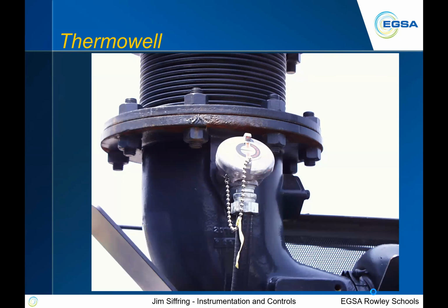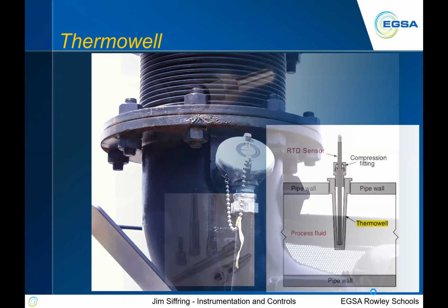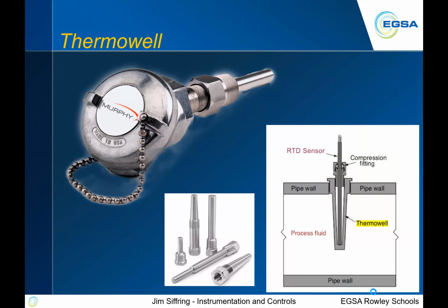A thermowell. So what is a thermowell? A thermowell is really a device that protects the sensitive electronic device, the thermocouple, sensor, RTD, whatever it happens to be, in that process, gas or fluid. So we screw that thermowell down into the pipe that is carrying that process gas, whether it's exhaust, whether it's coolant, whatever it happens to be, and then we put that sensor down into there. So the sensor isn't exposed to a nasty environment, exhaust stream or coolant or water or whatever it happens to be. The temperature will come right through. So it's really just a device to protect the sensor.